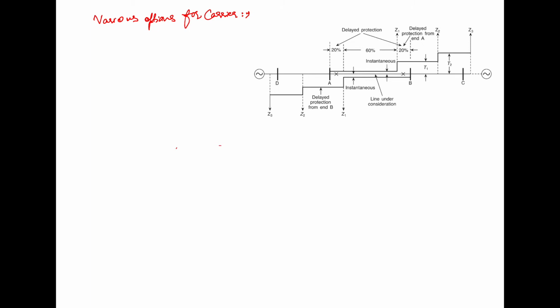Now, the various options for the carrier. The protective relay processes the information contained in the voltage and the current at the local end. The relay only indirectly infers the condition at the remote end through these signals. As the fault distance increases, the picture becomes more and more fuzzy. Hence, there is always an ambiguity about the exact location of a remote fault, and it becomes impossible to distinguish between a fault just beyond the remote bus and one just ahead of it.